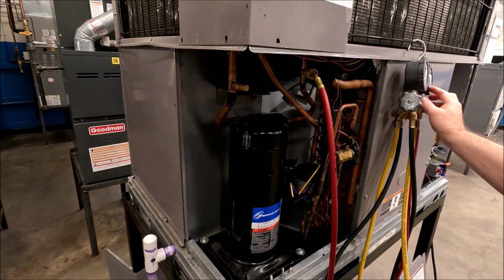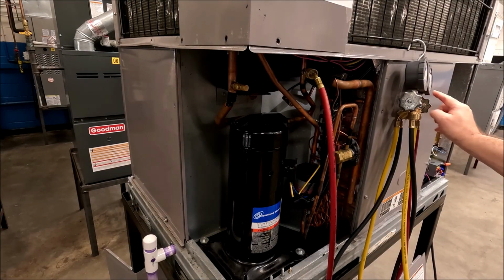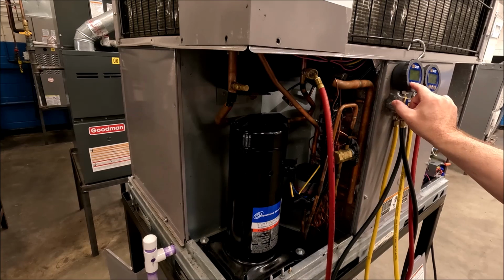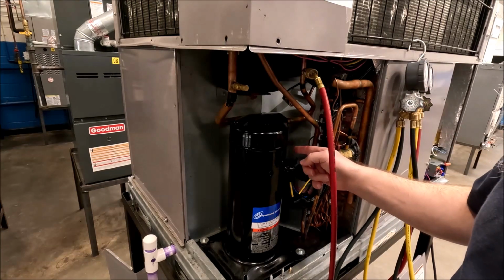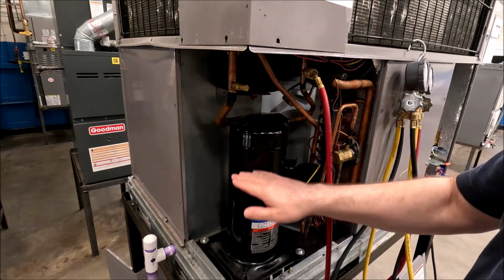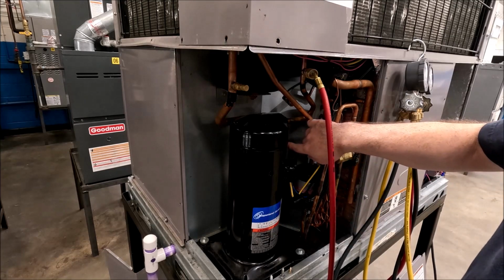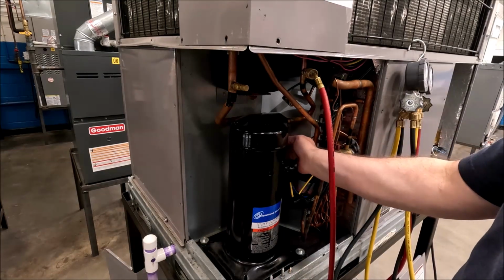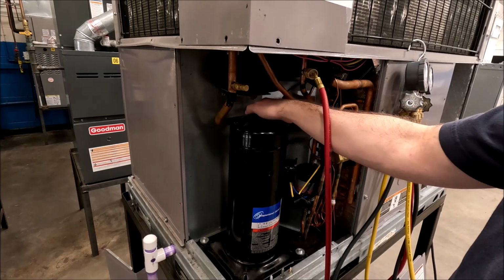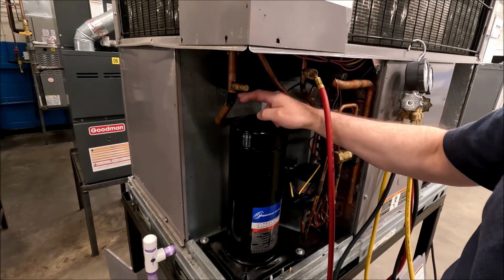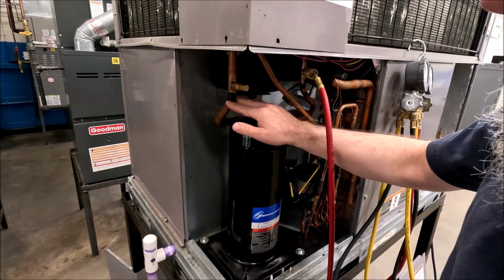Now the other side, since we've already taken care of the high side, we've got to take care of the low side. So you can follow that line from the lower portion going into the compressor. It's around back here, but if I follow it, it comes out a couple inches and curves up, and here it is right here. This is my vapor line coming from the evaporator.